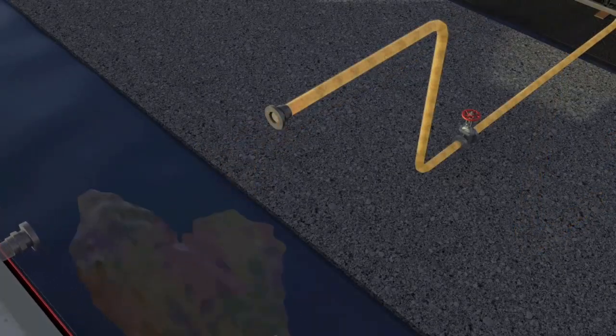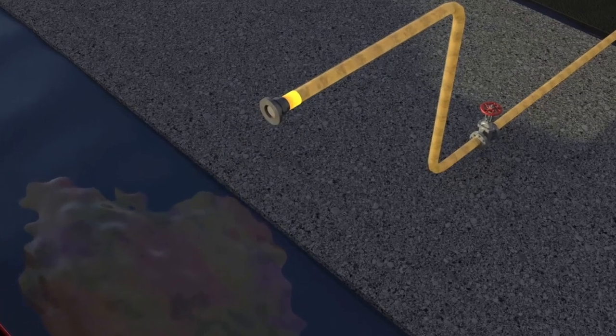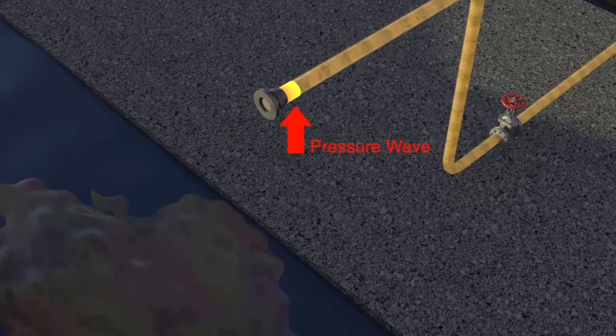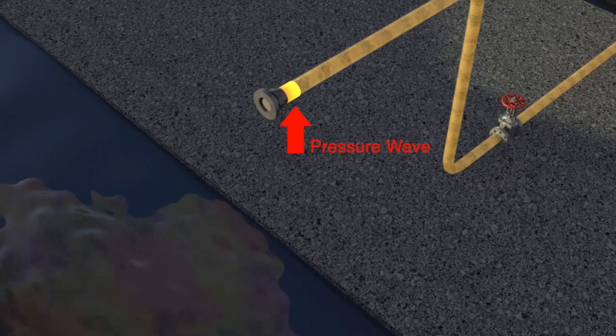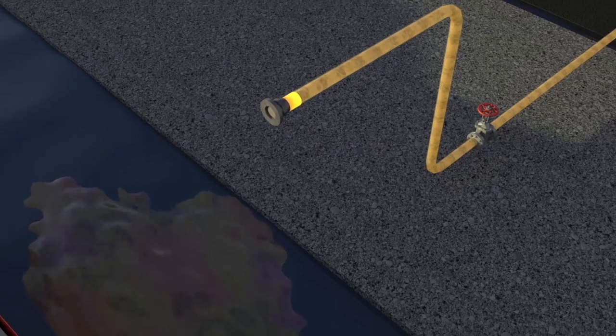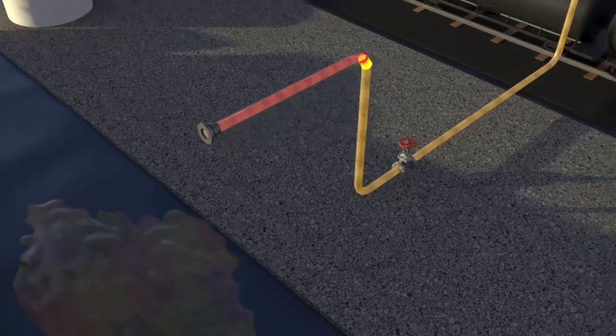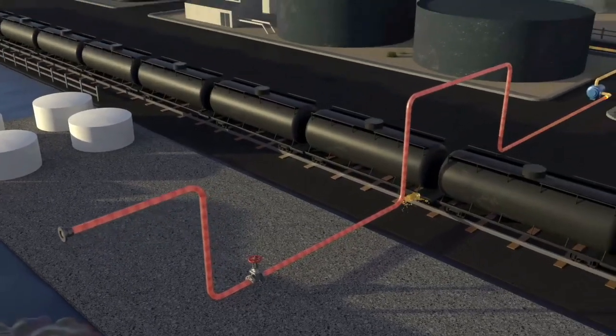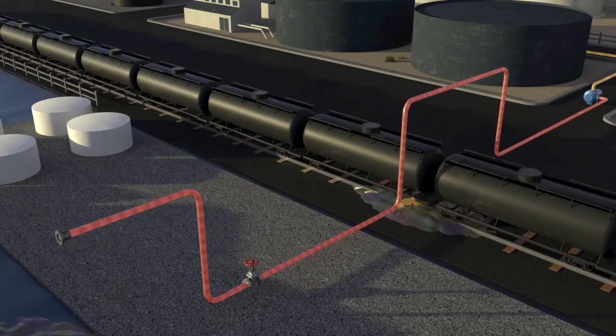A quick, two-second valve closure greatly minimizes the spill, however the immediate upsurge in pressure can easily exceed design pressures. The high-pressure transient wave initiated at the valve inlet travels backwards towards the pump at a speed near sonic velocity.